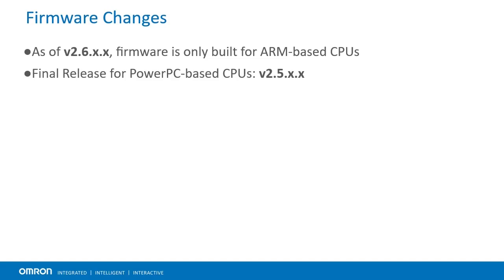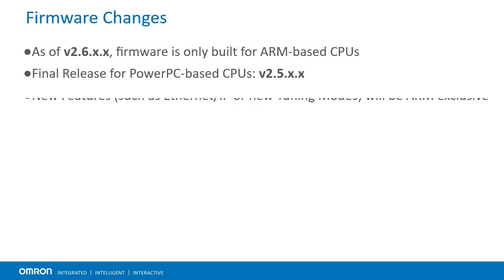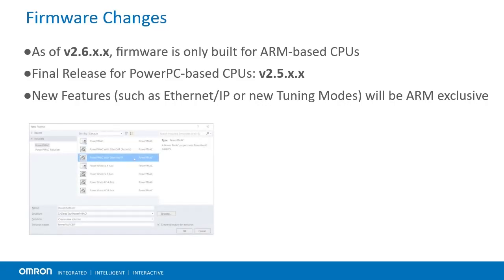Next, we will discuss the firmware changes. Firmware starting with version 2.6 will only be built for ARM Power PMACs by default. If new significant bugs or issues are discovered, new versions may still be released to address them on a case-by-case basis. However, new firmware features and improvements are only planned to be released for ARM Power PMACs. For instance, Ethernet IP is included automatically on any new ARM Power PMAC inside of the firmware. To get the same functionality on a PowerPC-based PMAC, the user would have to write the code to manage the communication themselves.